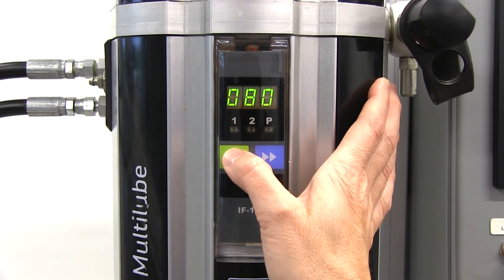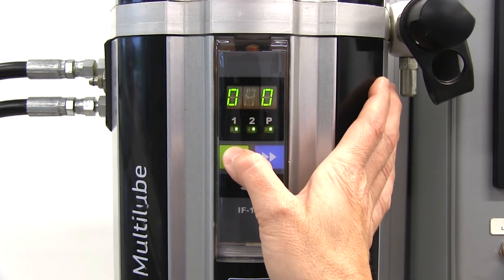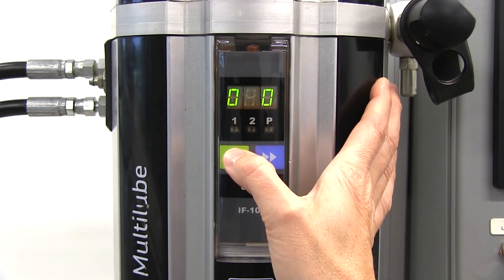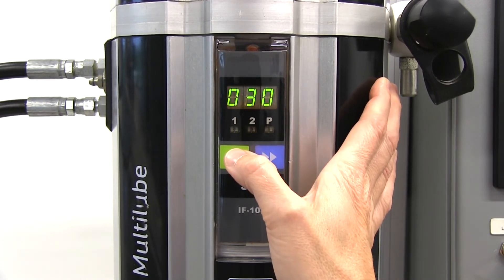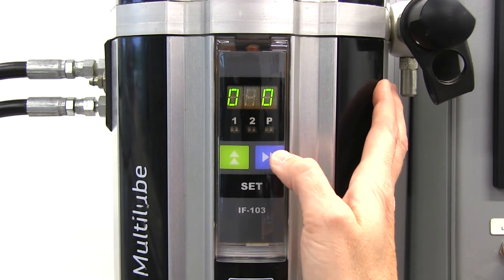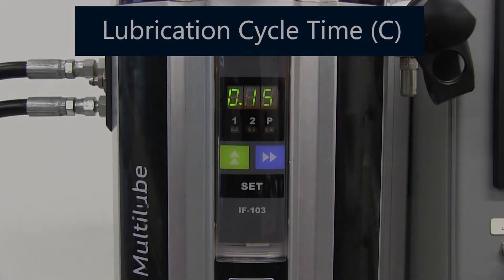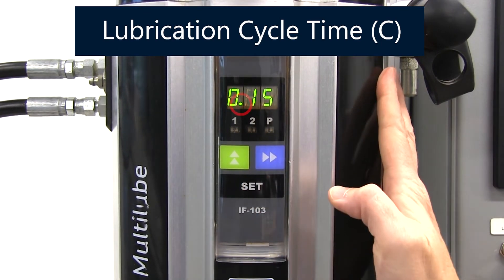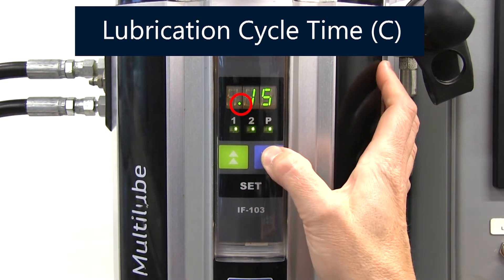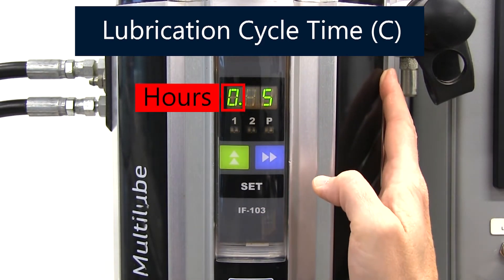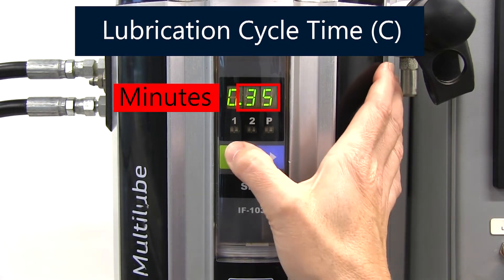Use the green up button to increase the number of the selected digit. The numbers cycle 0 through 9 and then back to 0 again. To proceed to the next digit to the right, press the blue right arrow button. For the lubrication cycle time (C) parameter, the decimal location can also be adjusted. Remember that hours are indicated to the left of the decimal and minutes are indicated to the right.